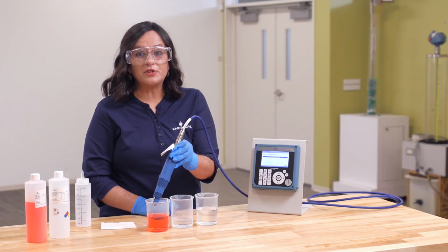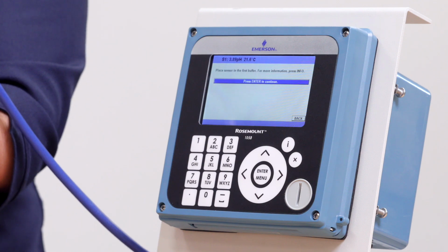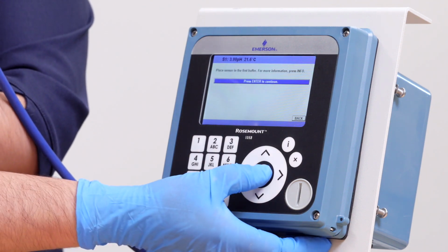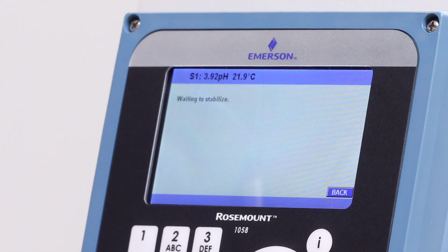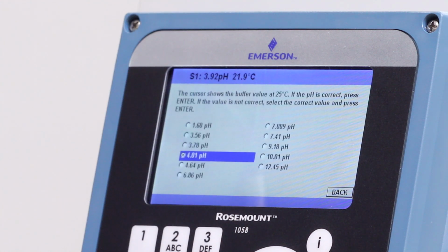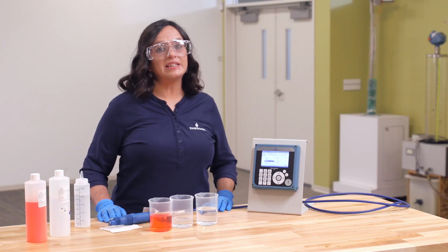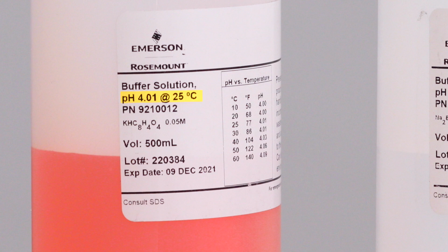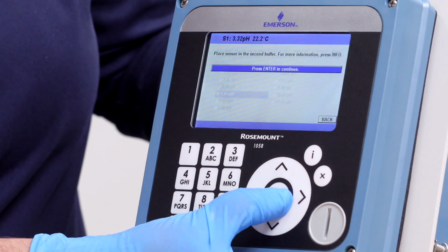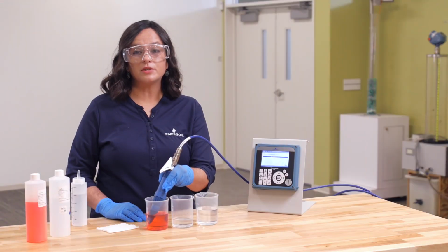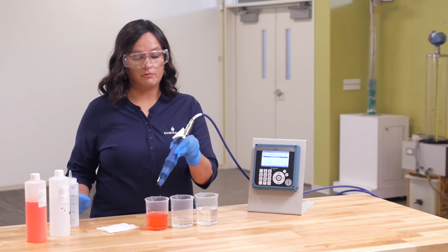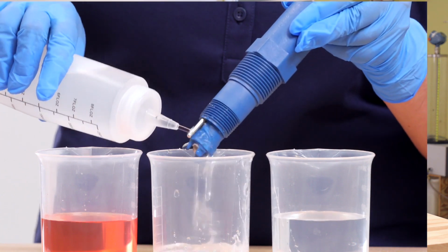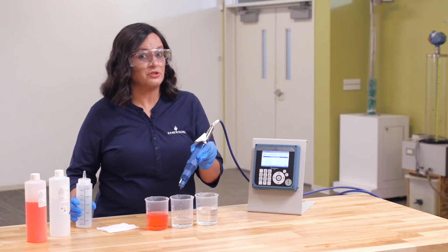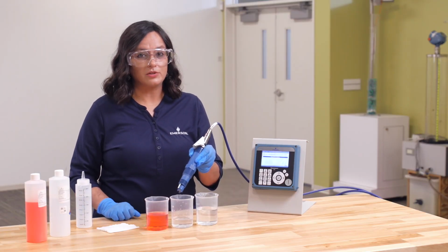Place the sensor in the first buffer solution and press Enter on the transmitter. Wait for the readings to stabilize. The transmitter will display a list of possible buffer solutions. Select the option that matches the label on the bottle. Now remove the sensor from the first buffer solution and rinse with tap water. Next, repeat these steps with the second solution.